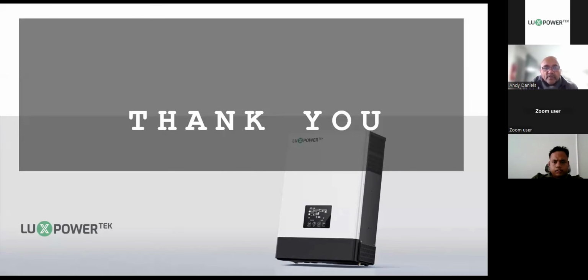All right, so Mario wants to know, is it not possible to install 5 kilowatt in one input and 3 kilowatt in another? No. I'm assuming, Mario, you're asking about the PV. No, you cannot do that. Even though your combined strings total 8 kilowatts, you cannot exceed 4 kilowatts on any input. So unfortunately, you're going to have to reduce the 5 to a 4 or do something, but you cannot do that. It's going to damage the MPPT.